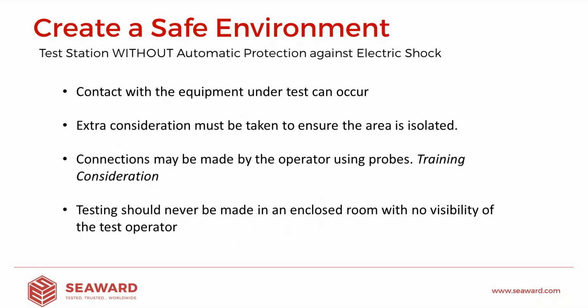So the other way you could look to set up an area, and it's probably more common, is a test station without automatic protection against direct contact. Effectively, there's nothing stopping the operator from touching the item under test. Again, from a practical point of view, it may be that this is the only method you have to set up. Talking about temporary test stations, you may have to go to the equipment itself in order to perform the test. So you may have to take the individual elements with you in order to create a safe working environment. So we know we can come into contact with it, and therefore we have to take extra consideration to ensure that the area in which we're going to be doing the testing is fully isolated.